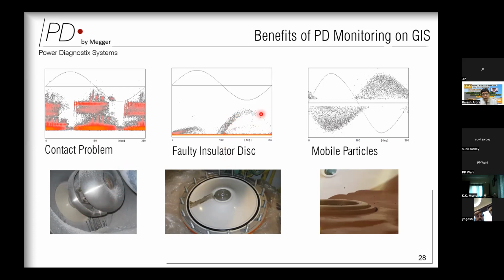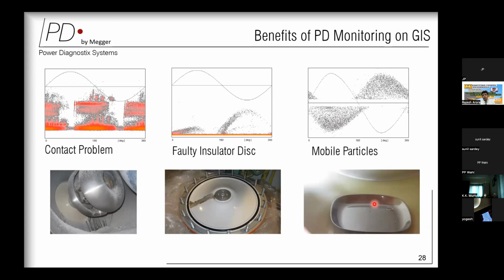Now this particular pattern is due to the faulty disk insulator, and if it is not taken care of, we can see the sparking which has happened inside the GIS. The right hand side pattern is generated because of the moving particles, and if we look down below with the visible eye from the monitoring window, we can see there are some dust particles moving inside the GIS. Now there is a video which is visible over here. I'm not sure whether you can see, but this is an example of moving particles. If there are any dust or metallic particles inside the GIS, then they start dancing under the influence of high voltage, and they will jump from the GIS enclosure towards the conductor, and they will create a path between the ground potential and the high voltage potential, and they act as a catalyst to create the sparking inside the GIS.